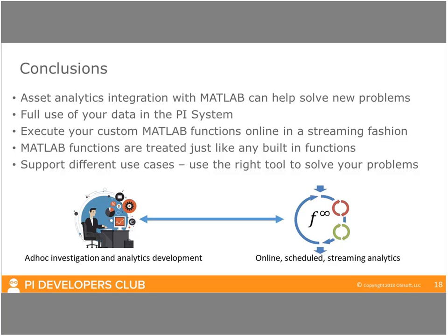However, if you're an engineer and you're trying to investigate, you're researching, you're trying to find a mathematical solution to your problem, you wouldn't do that necessarily from within AF, but rather you would use some other native tools that support ad hoc batch type investigation. So in this particular case, you would probably want to use the native MATLAB client tools to build these functions, to do your investigation, grab some data from the PI system, build up your logic, build up your script. But once you're happy with it, all you need to do is compile it, drop it into the auto-deploy folder, and you can pick it up in AF and run with it in a streaming fashion, just like that.